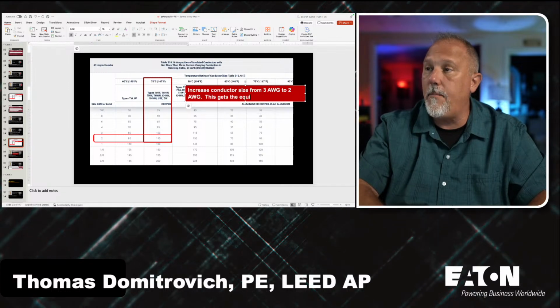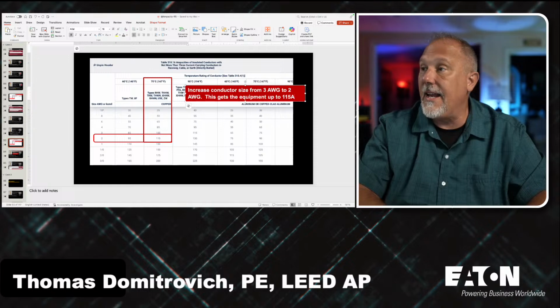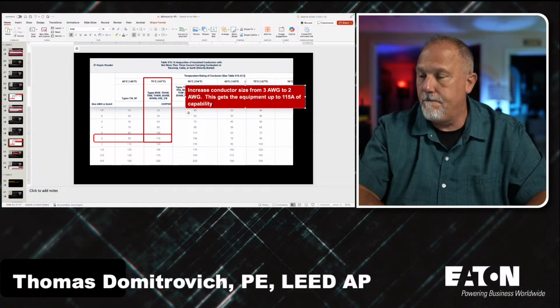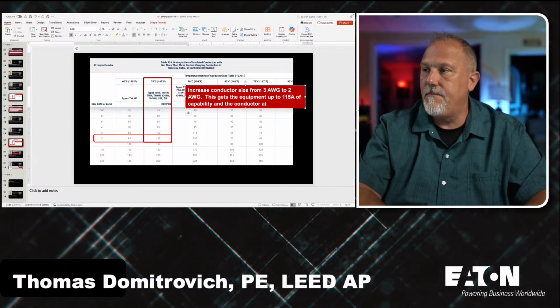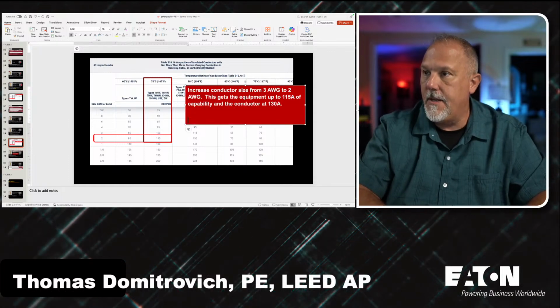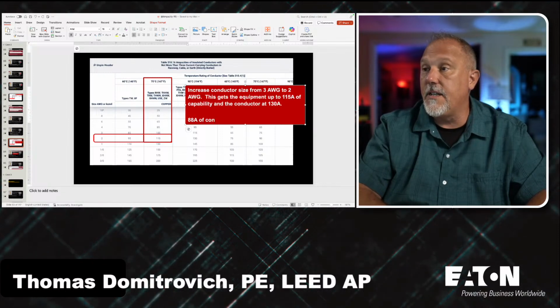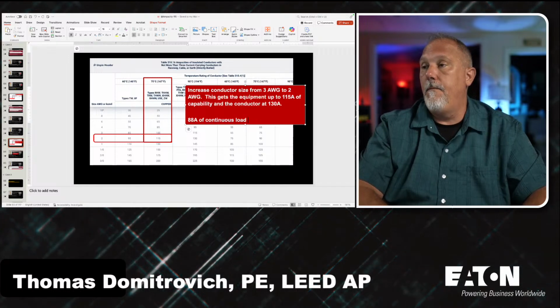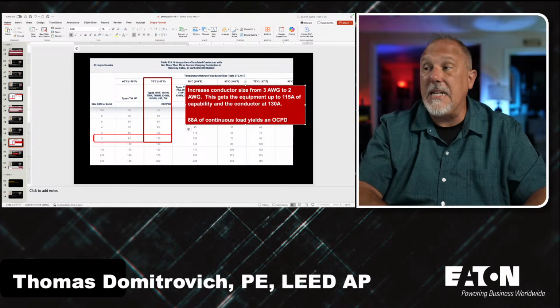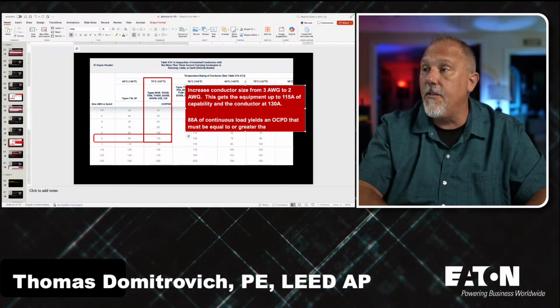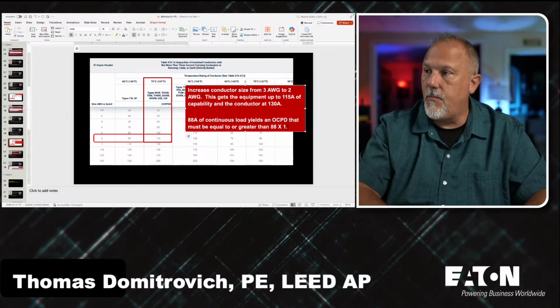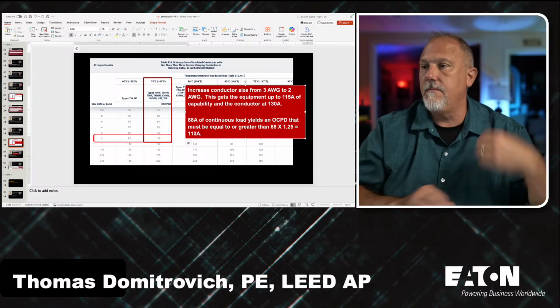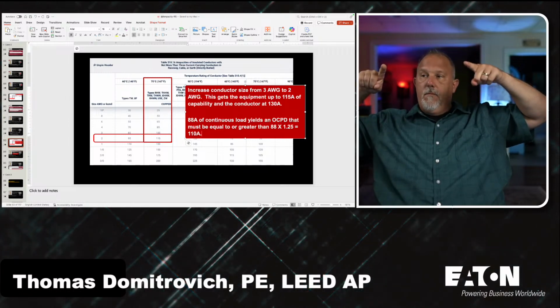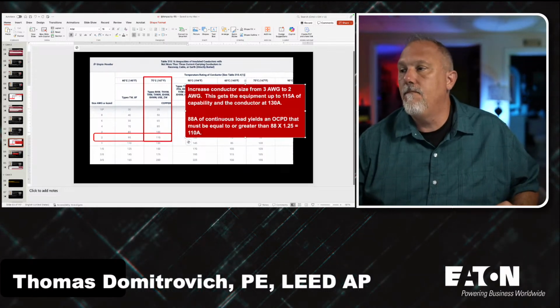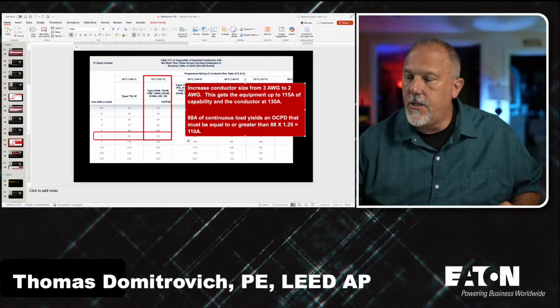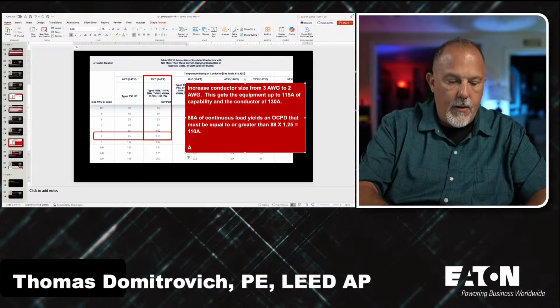This gets the equipment up to 115 amps of capability, and the conductor at 130 amps, period. 88 amps of continuous load yields an OCPD that must be equal to or greater than 88 times 1.25 equals 110 amps. So I could put a 110 amp breaker on here. And 110 amps is a good one. A 110 amp circuit breaker.